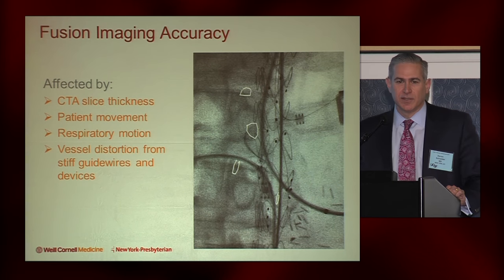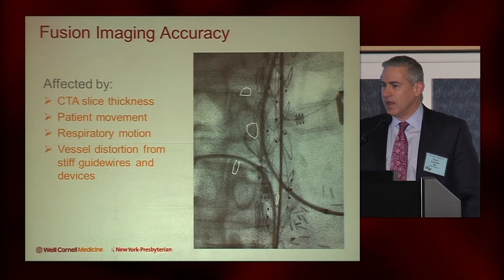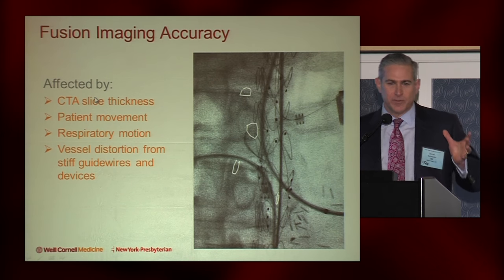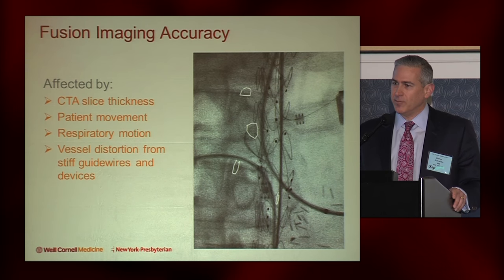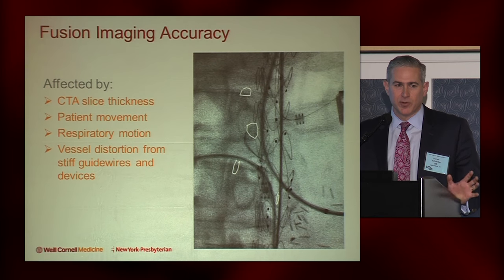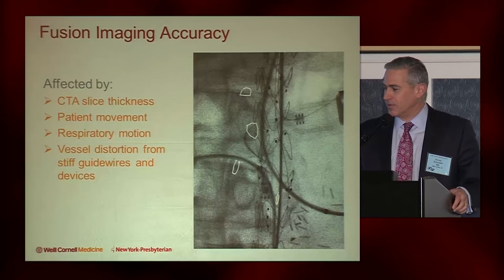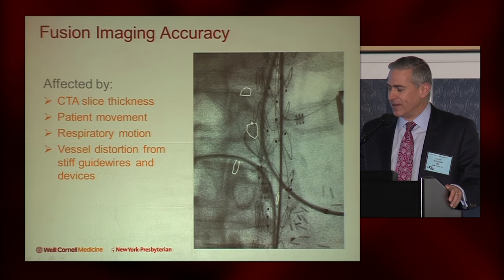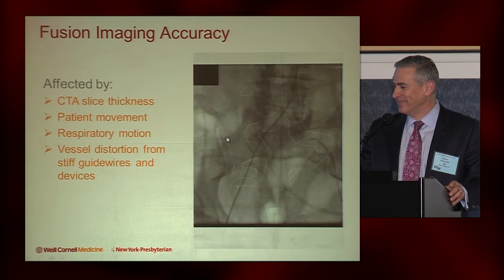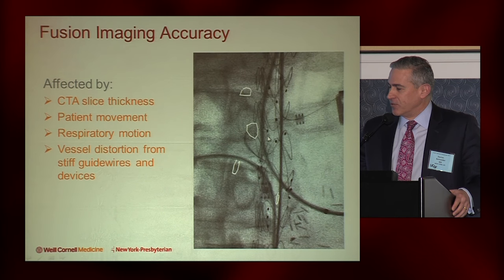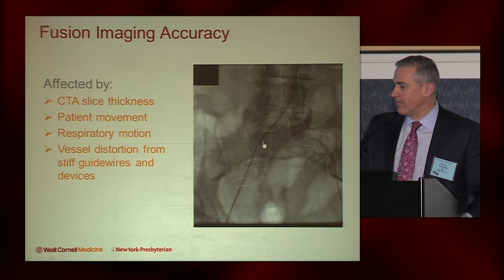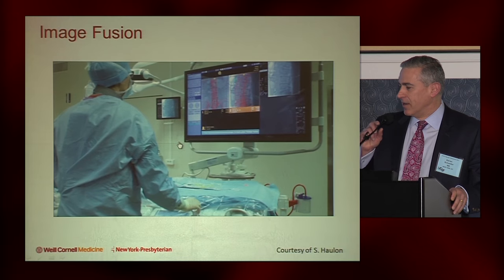There can be some issues with accuracy using the different systems, and they do differ whether you're on a Siemens, GE, or Philips system. Accuracy can be affected by the quality of your CTA preoperatively, the slice thickness, patient movement — if the patient moves on the table or if you move the patient after the cone beam CT while prepping, that can throw registration off. There's also respiratory motion, particularly of the renal arteries, and vessel distortion from stiff guide wires and devices. Here you can see a stiff sheath or guide wire straightening those iliacs, so overlays looking at the iliacs, the renal arteries, or a really angulated neck can be modified by the stiff angles.